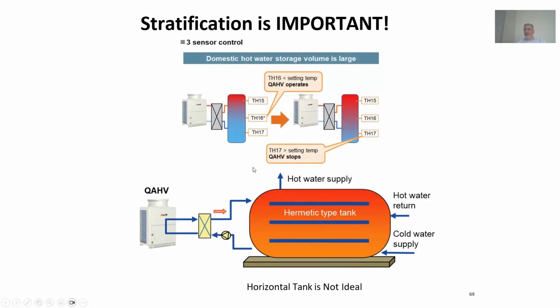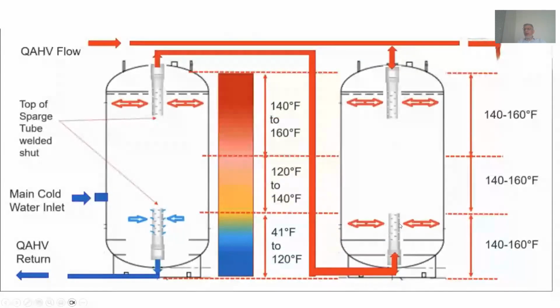On the storage tank, it is recommended the tank should be a vertical type, not a horizontal type, because we want to maintain stratification. That's the most important aspect of this one. Stratification will be happening in that your temperature on the bottom side will be low because the cold water from the city is coming at the bottom. Since the hot water is coming on the top, there will be, let's say, 160 to 140 temperature coming at the top, and 120 to 140 at the mid-size, and at the bottom, since the water is coming there, 41 to 120 Fahrenheit.